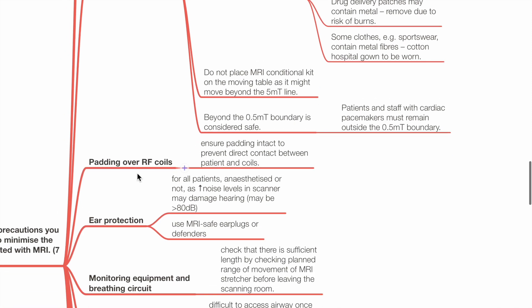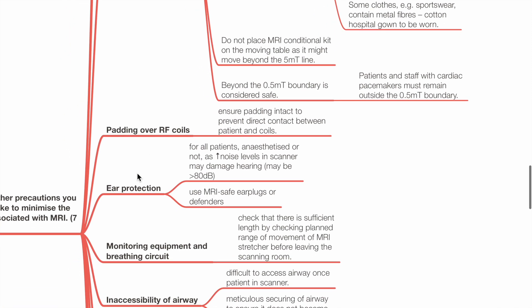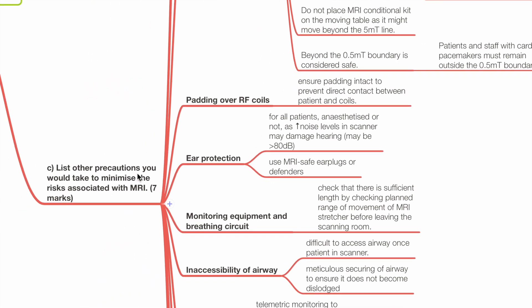Do not place MRI-conditional kit on the moving table as it might move beyond the 5 mT line. Beyond the 0.5 mT boundary is considered safe. Patients and staff with cardiac pacemakers must remain outside the 0.5 mT boundary. Ensure padding is intact to prevent direct contact between the patient and the RF coils.